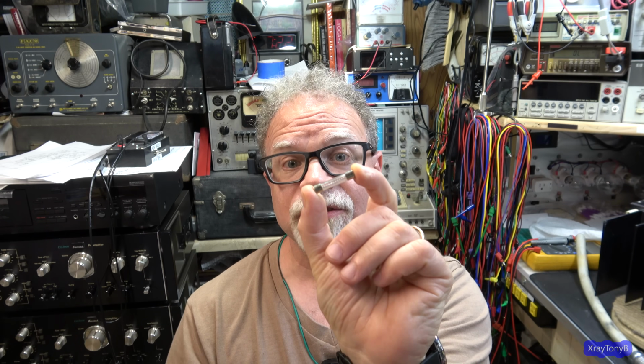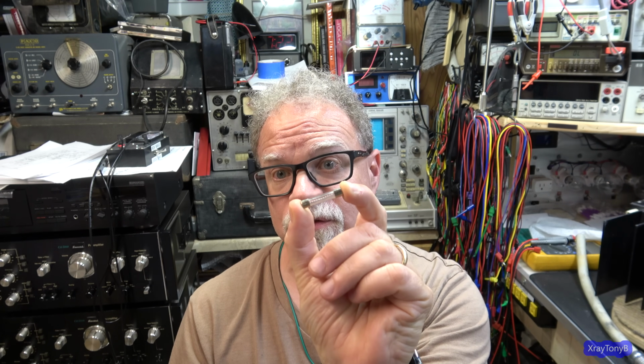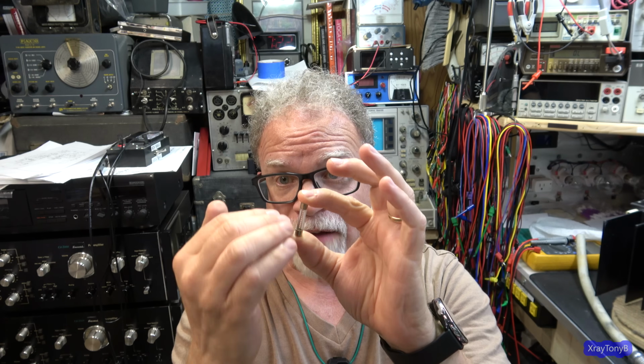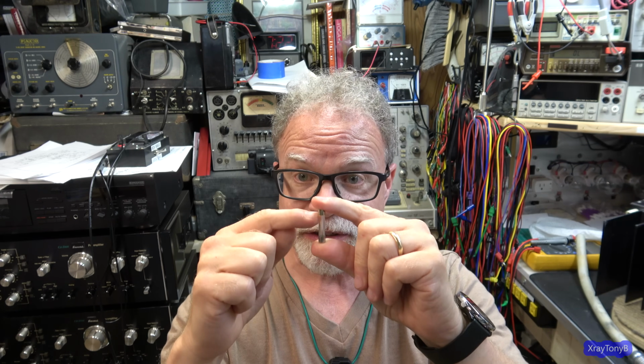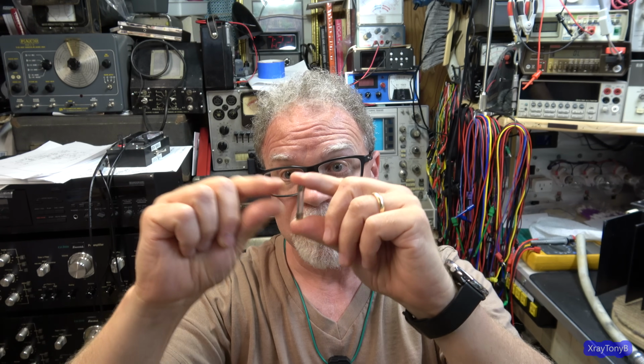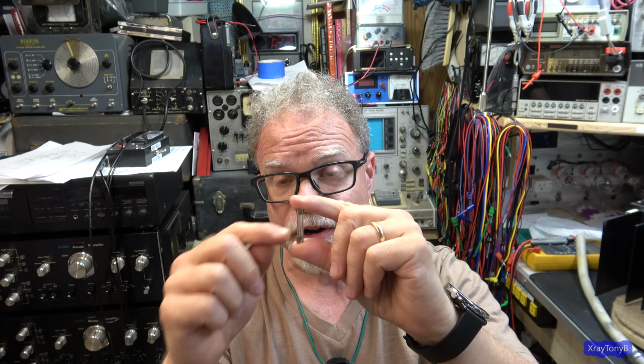It has resistance. So there is a voltage drop across the filament of this fuse. And as it heats up, once it gets to a hot enough temperature that the metal softens to the point where it'll rupture and open, that's when it breaks the circuit. But then you go from a very low impedance circuit in here to a very high impedance circuit, and you're doing it all at once. As soon as that filament breaks open, whatever potential was at the circuit is now across this fuse, because it's open circuit. It's high impedance now, very high DC resistance, right?